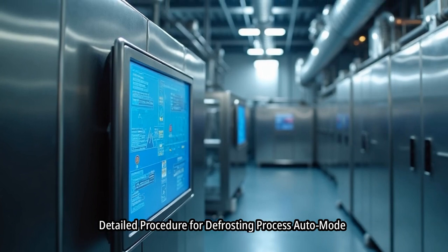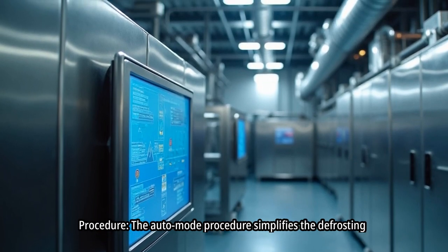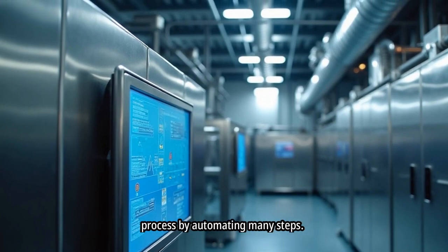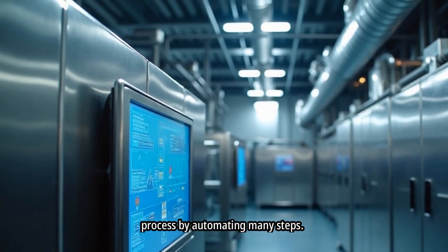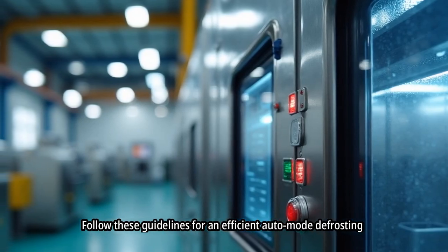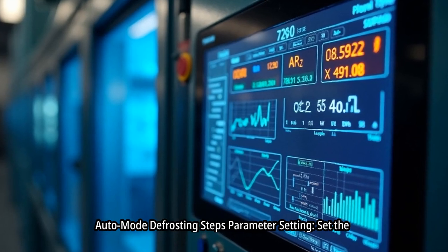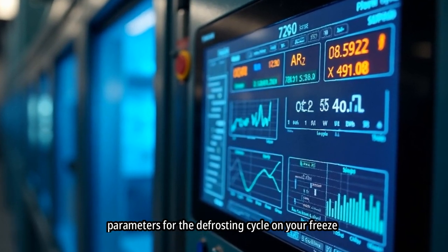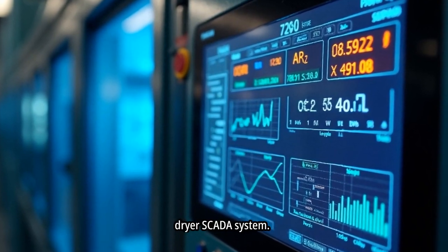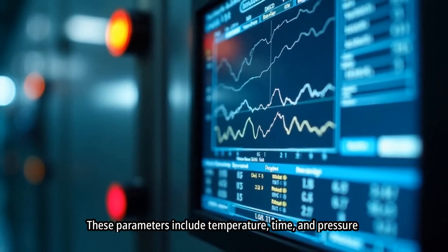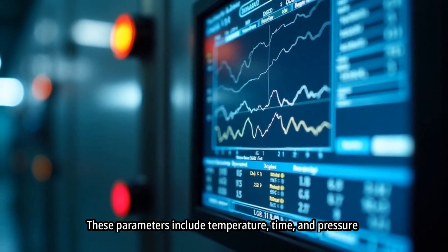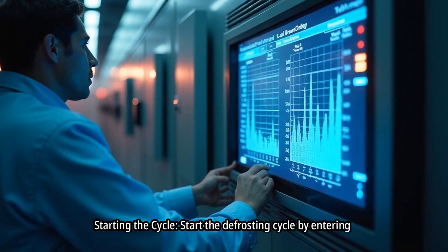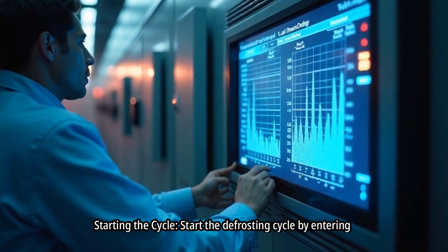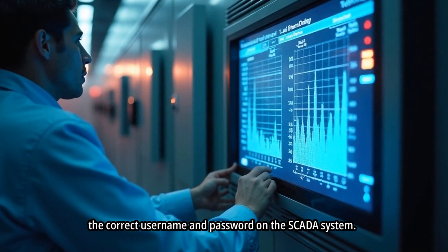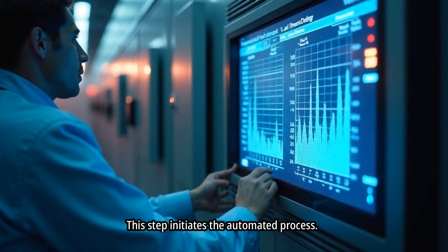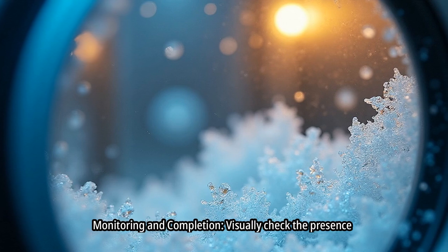Detailed procedure for the defrosting process: auto mode procedure. The auto mode procedure simplifies the defrosting process by automating many steps. Follow these guidelines for an efficient auto mode defrosting cycle. Auto mode defrosting steps: parameter setting. Set the parameters for the defrosting cycle on your freeze dryer SCADA system. These parameters include temperature, time, and pressure set points. Starting the cycle. Start the defrosting cycle by entering the correct username and password on the SCADA system. This step initiates the automated process.